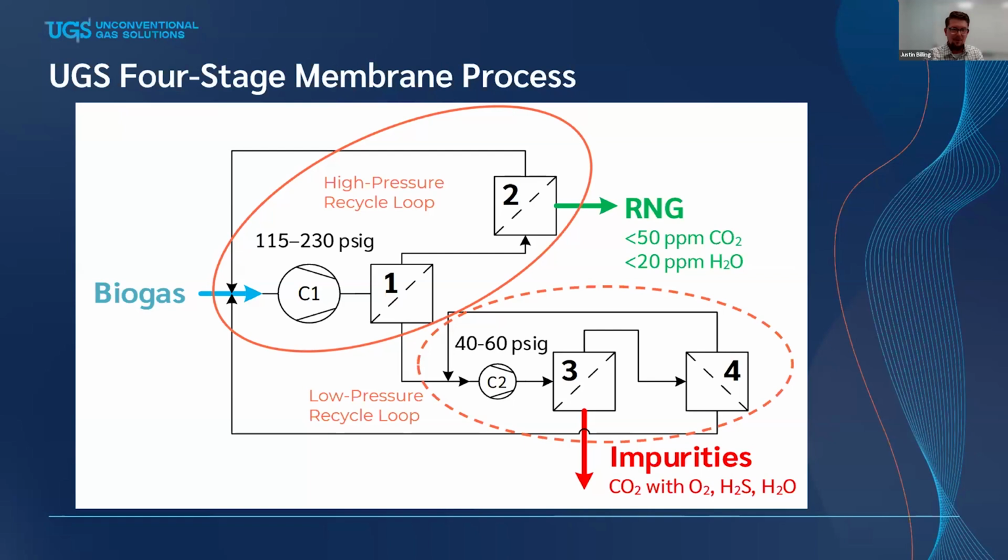So it's possible with using UBE membranes and a standard PSA NRU that you would end up meeting pipeline specification for oxygen if it's the more typical specification of 0.2% oxygen. If it's lower, then you still may need a deoxo. So there's enough of an advantage to make us and others take a second look at the UBE membranes. They get a little extra oxygen separation there.